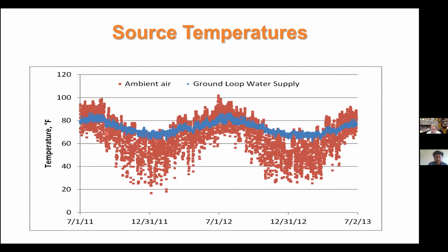So of course, these are the source temperatures. The blue dots here represent the returning ground heat exchanger temperature over time. You can see it's very moderate. It peaks around maybe 85 degrees, and the minimum is maybe somewhere around 65 degrees. And of course, the red is the ambient air, and as always, it varies a lot more than the ground temperature.